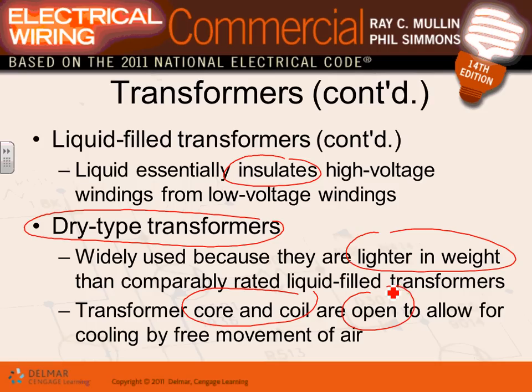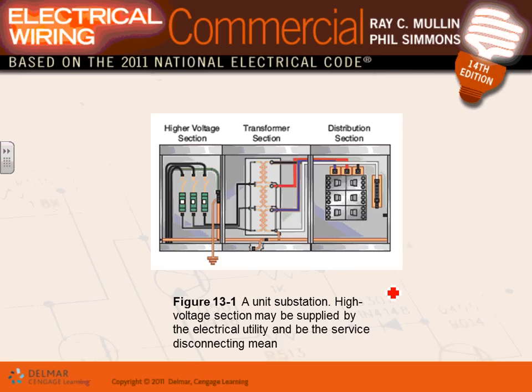They have big, huge fans, guys, blowing air right into the transformer to cool it. I can't emphasize enough, guys, that the important thing for a transformer to work properly is to keep it cooled. You don't want to confine it. Most of the transformers that we use in the electrical construction industry are dry type transformers. Utilities use oil filled transformers. They perform better, they live longer, and they can be abused more.